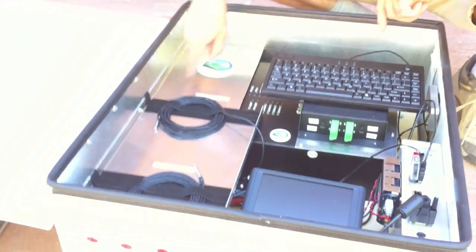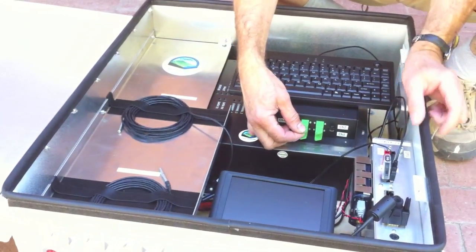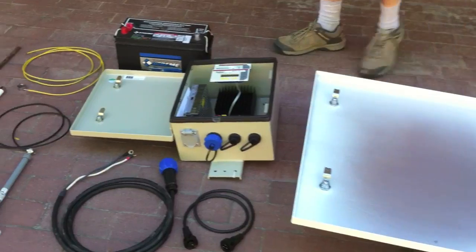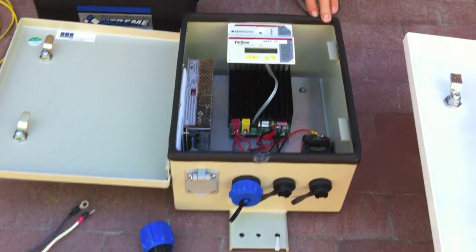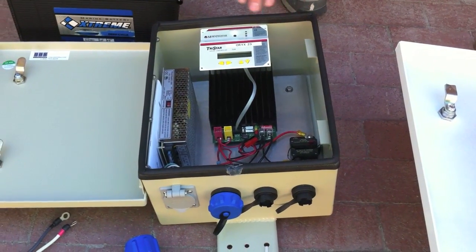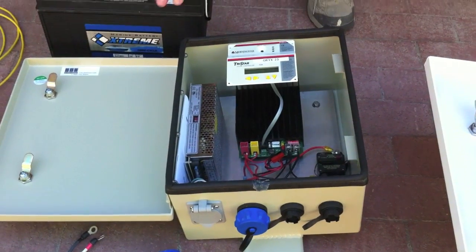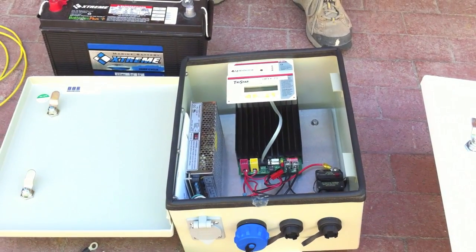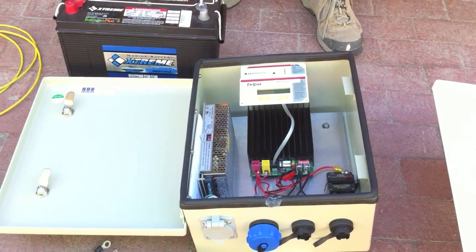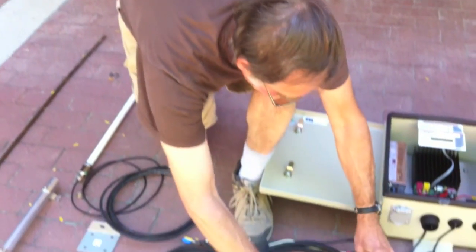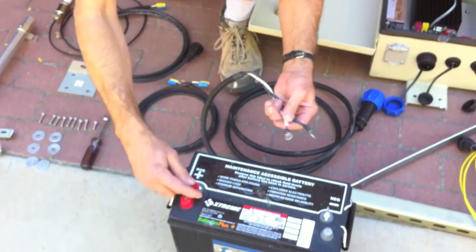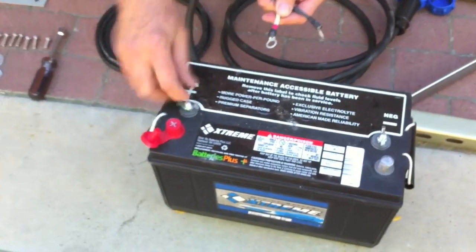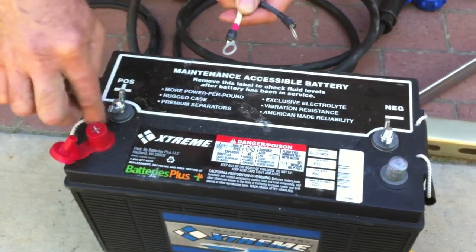The fiber optic cables are then plugged into this junction box here. We have the power box assembly. So this supplies power from the solar panels to charge the battery and then power to the DTS box. We're going to connect the battery so we can look at the display on the solar charge controller. So the two leads for the battery are marked red for positive and black for negative.